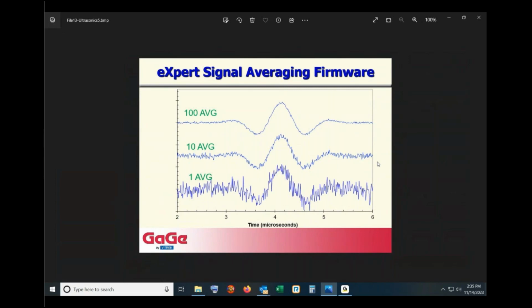Now, as I say, GageScope does averaging in software. So to get 100 averages, it'll download 100 waveforms, sum them all together in software, and present the result. But what the GaGe card is able to do, with a special expert firmware option for signal averaging, is to actually sum the waveforms up on the card itself. It does two things. It alleviates the task of doing the averaging from the host computer, but more importantly, it dramatically reduces the data volume.